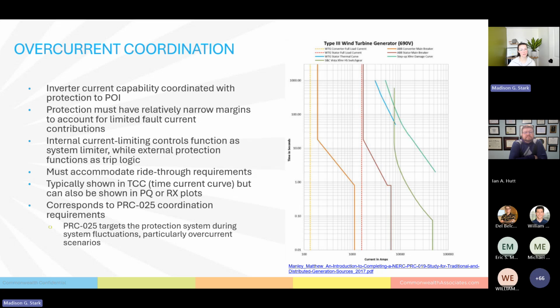What we see all the way on the right side are basically your substation elements that connect both of these points to the main grid. Actually, I lied. This is the stator thermal curve, the thermal limitations that this red breaker is protecting. This right here is the step-up transformer, taking the aggregate current from both of these components and pushing it out to the grid. This is our switchgear, where both of these currents connect, and then they go to the step-up transformer and out to the grid. These are your substation type elements on the POI, the point of interconnection side of the house. And then this right here and this right here are the 2 generating elements for the type 3 wind turbine generator.